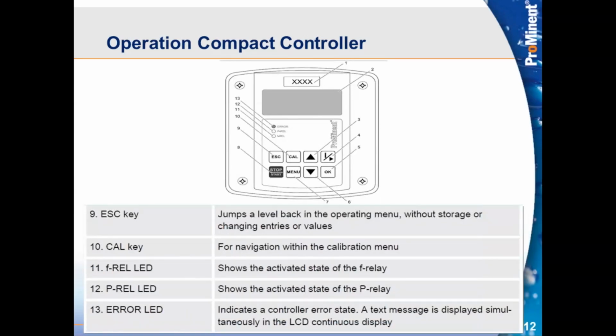An escape key, so it kind of works opposite of the OK key in a sense, where OK verifies that you want to accept the changes you made. If you get in a menu and you sort of get lost, or you're not familiar with the changes you made and you don't want to accept them, you can hit the escape key to go back a level in the menu. We have the calibration key. That's kind of a nice feature we've been seeing on most of the new equipment. It's a shortcut to go into the calibration routine, and usually the screen is going to tell us when to hit that button next during that calibration routine.